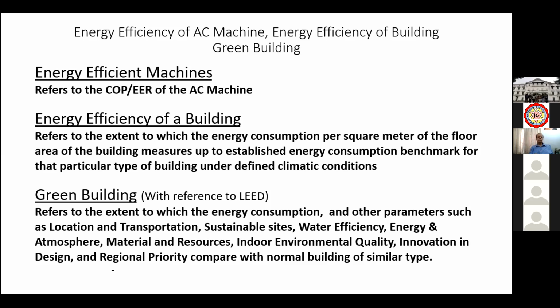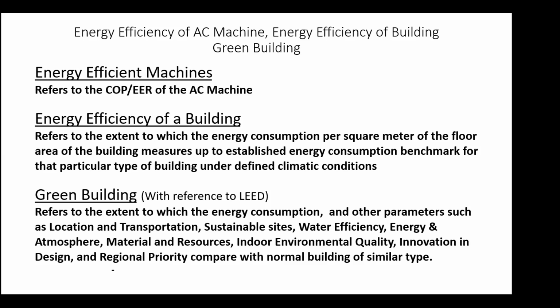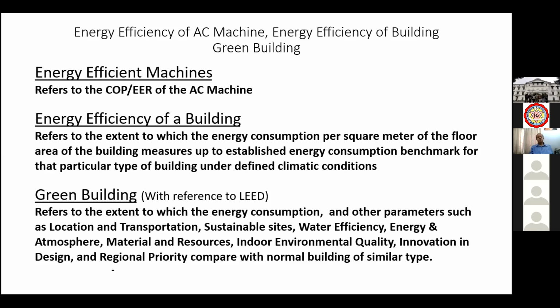Energy efficient machines refer to the coefficient of performance, COP, or energy efficiency ratio, EER, of the AC machine. By COP, we mean the air conditioning machine operates as a heat pump. Now, if you supply 1 kilowatt of power to the machine compressor and get 4 kilowatt equivalent of heat, then the COP is 4. Modern machines have a COP range of 3.5 to 4, VRV machines. That means if we operate a 1 kilowatt resistance heater, we'll get at most 1 kilowatt heat output. But with a 1 kilowatt AC machine, we'll get at least 3.5 kilowatt heat output. That is the energy efficiency of efficient machines.